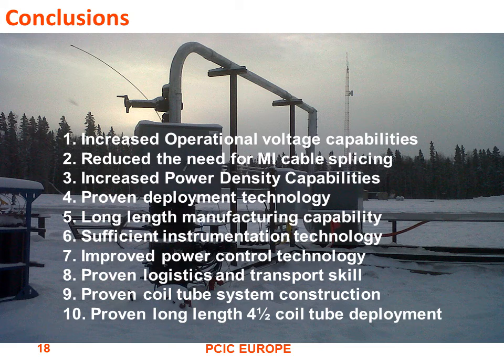As I said before, it's usually limited to the 600 volt and under regime, and now we have tested, verified commercial heaters that can operate at, this one operated at 4160, and we think we can characterize it at 6,000 volts on a Y connection.